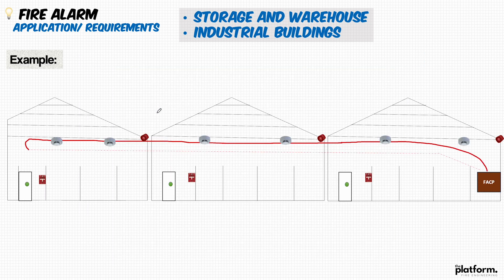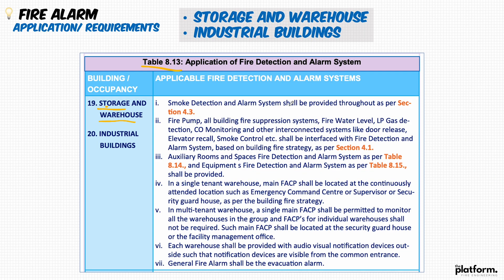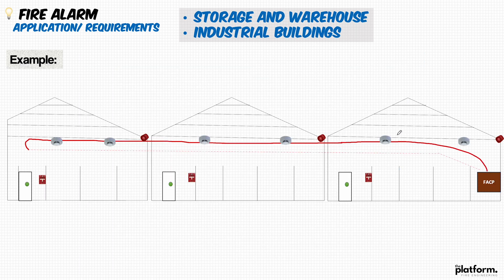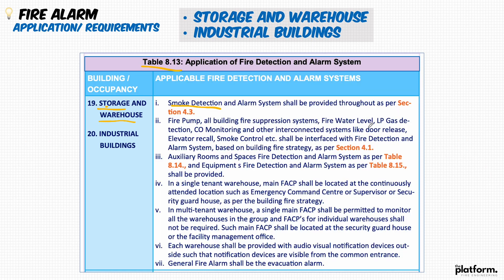I have drafted a quick layout for three warehouses connected together. We will be reading point by point and then try to apply it to this layout. Point number one: a smoke detection and alarm system shall be provided throughout, as per section 4.3 — which relates to installation distances and spacing. So smoke detection is required. I have provided a smoke detector in each warehouse. The distances between smoke detectors and the type of devices shall follow what we covered in this course and what is mentioned in the other sections.